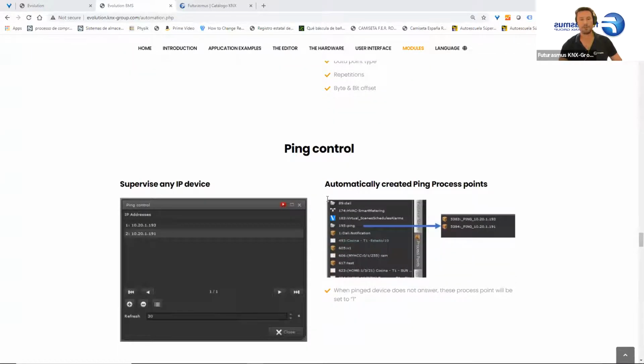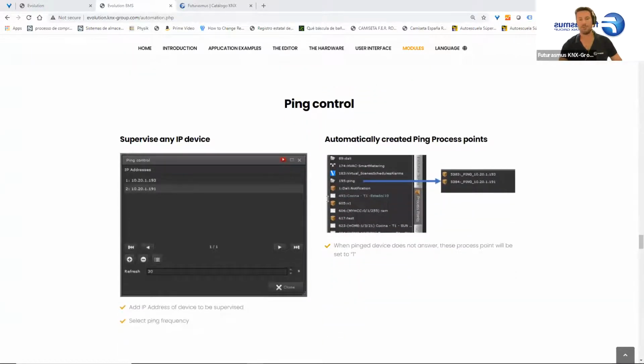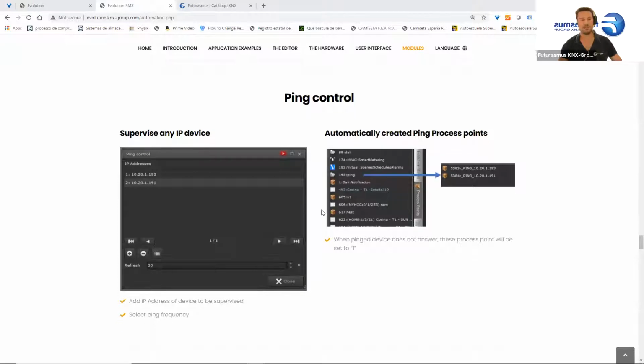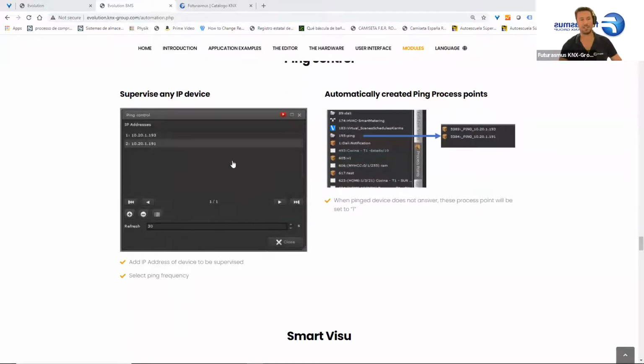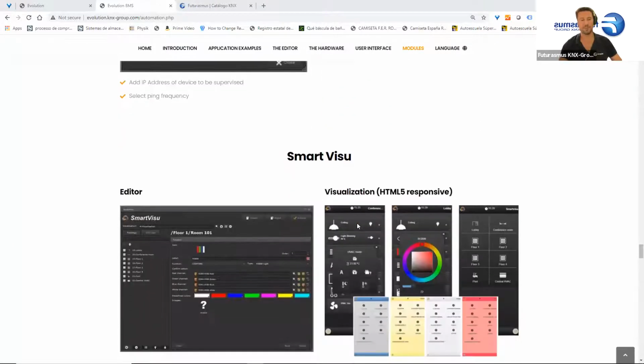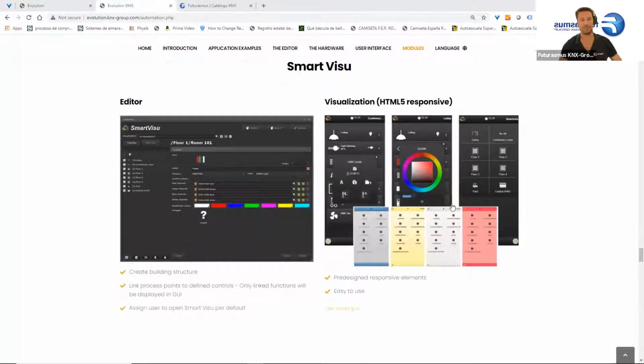You can have a ping control where you can supervise IP devices. So you set up the ping commands, and it will send ping messages to the IP addresses. You can set up the cyclic frequency for this ping. If the IP address responds, it will be a 0, and if it doesn't respond, it will set the bit to 1, saying that there's an error in this device. This is the user interface for the smart visualization, for instance.